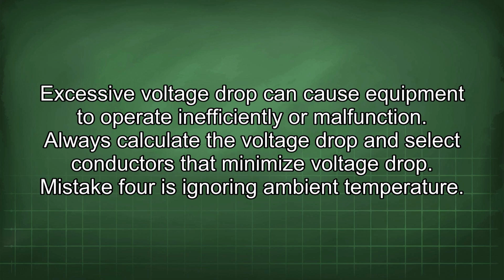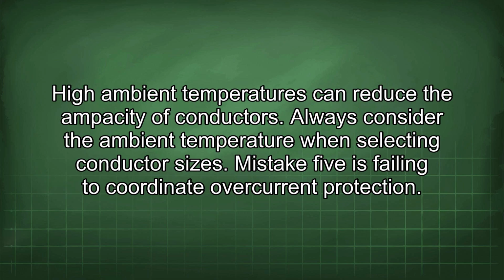Mistake 4 is ignoring ambient temperature. High ambient temperatures can reduce the ampacity of conductors. Always consider the ambient temperature when selecting conductor sizes.